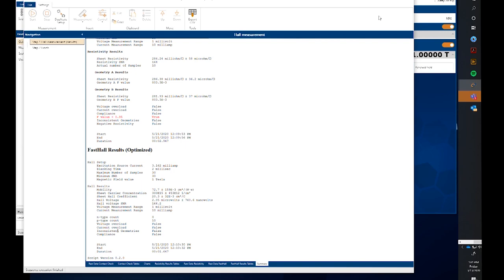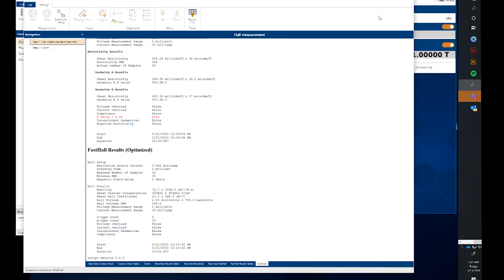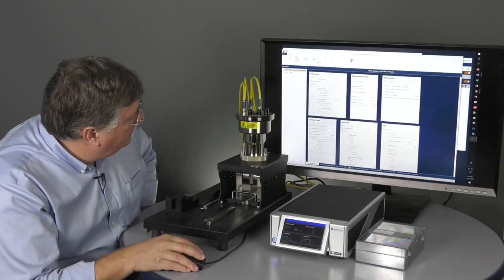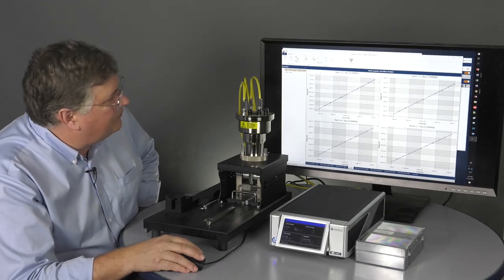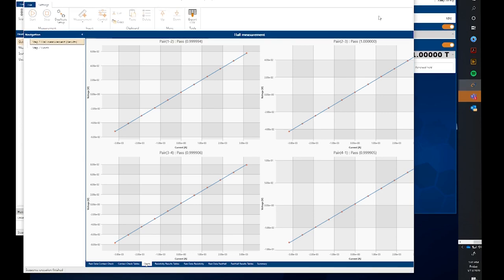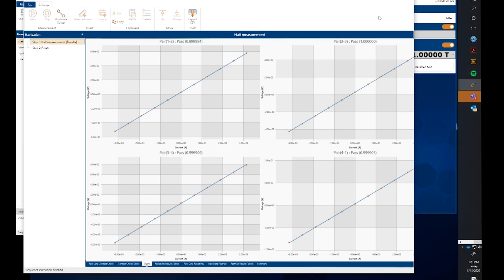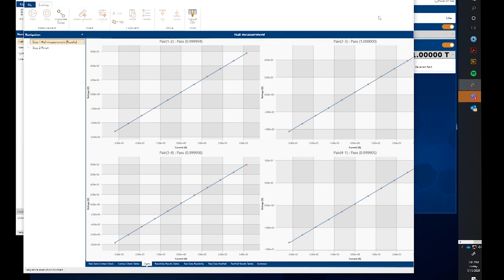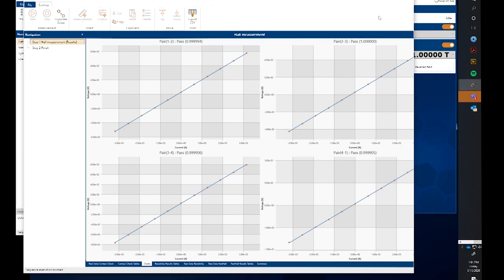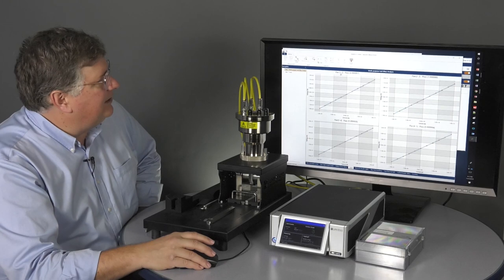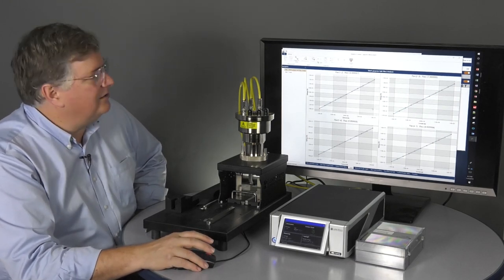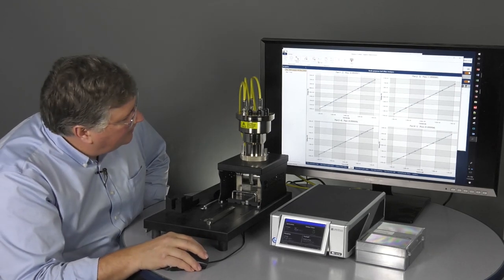Also included in this data file are, so we have the initial setup for how the system was run. We do also have our charts. So these are the four charts for the contact checks. This is particularly useful to view if one of your contacts was not made properly. You could see, in other words, if contact one was not made properly, you would see it show up in this 1-2 contact check and 4-1, these two. These other two may be just fine. So if you can look and see the common number between the two that are bad, you likely can just go back and adjust one of the contacts, make that.